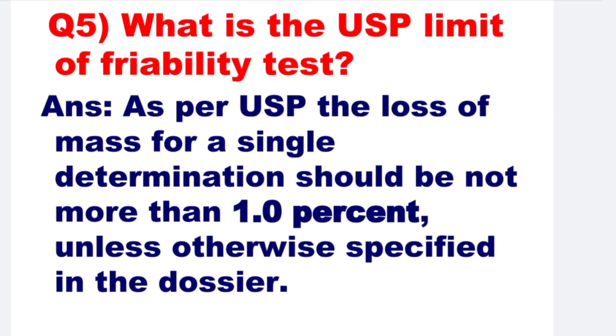Next: What is the USP limit of friability test? As per USP, the loss of mass for a single determination should be not more than 1%, unless otherwise specified in the dossier.